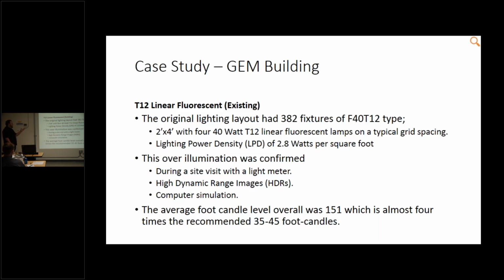The original layout had 382 fixtures, 2x4 with four 40 watt T12 linear fluorescents. The over illumination was confirmed during a site visit with a light meter. You could kind of tell just by walking into some of the spaces, it was pretty bad. The average foot candle was 151, about 4 times the recommended value of 35 to 45.